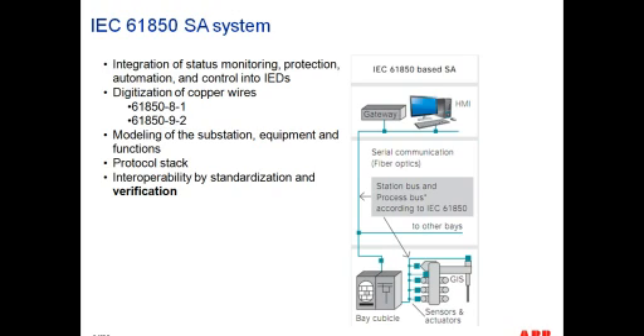And what these are is, in the case of GOOSE messages, a high-speed communications protocol that enables the exchange of horizontal information from one relay to another relay on a real-time basis. And then 61850-9-2 is actually a protocol that enables the digitization of current signals and voltage signals, and then the publication of those currents and voltage signals onto an Ethernet network for their real-time deployment, so that relays could operate their protection functions based on these digital messages rather than utilizing currents and voltages that would be wired up in the form of copper wires from your current transformers and voltage transformers. And that specifically is the topic of today's presentation.